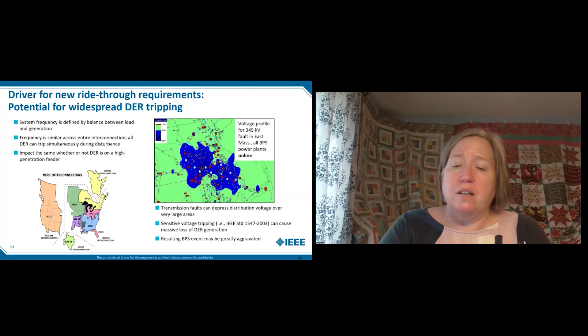The other piece of it is that where we're really interconnected, transmission faults can result in a wide area voltage depression. And if the DER is set too sensitive, or set at defaults, depending on how large and how long that depression is, you can start dumping DER, which will aggravate that event on the transmission system. So we really don't want to do that. It's really about maintaining a balance between grid safety and bulk system reliability.